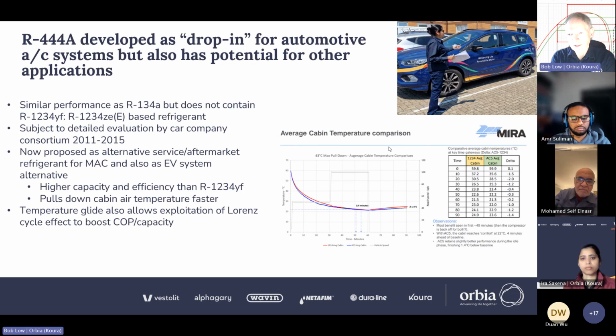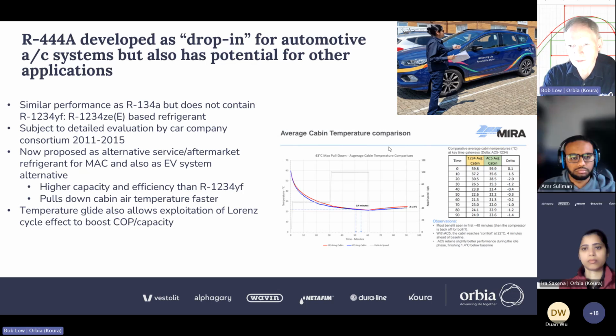The other point to note is that in the steady state, when the control system lines out and goes into steady operation, it's consistently delivering colder air than YF. So in terms of passenger experience, colder air faster. We're proposing it for automotive service as a cost benefit primarily to the end user, but for original EV build, it's also got attractive features for heat pump mode. It's a higher pressure refrigerant than 1234yf, so it can actually go colder in heat pump mode than YF can. And as it doesn't contain 1234yf at all, it won't make trifluoroacetic acid in the environment.